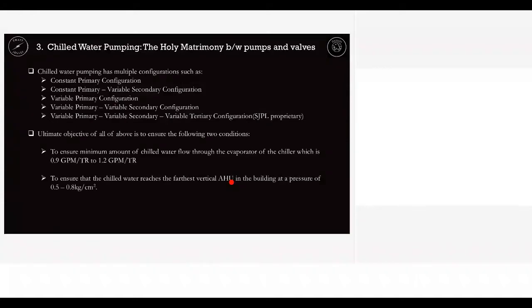And then there is variable primary. That means one pump itself serves the duty of circulating water through the plant room as well as ensuring that the water reaches the farthest corners of the building where centralized air conditioning is feeding. And then there is variable primary, variable secondary, and a lot of sophistication. The point is, in centralized air conditioning, what is happening? You are generating cold water in your plant. You are taking this cold water to the different parts of the building by pumping it.